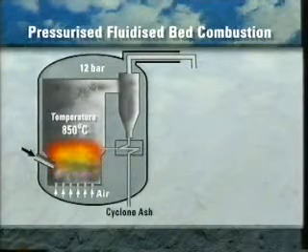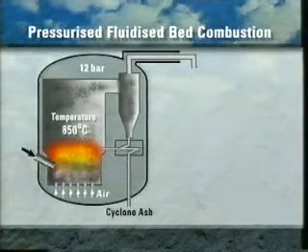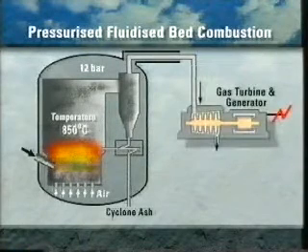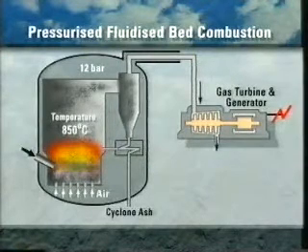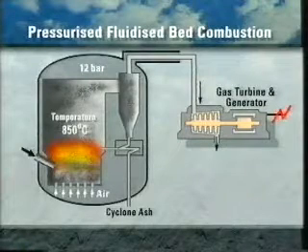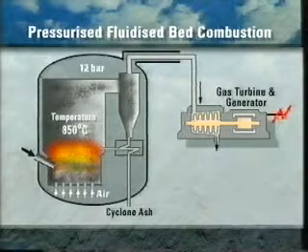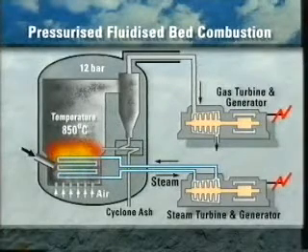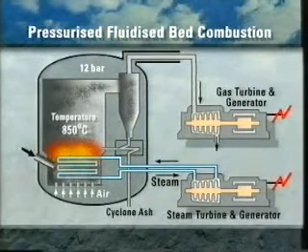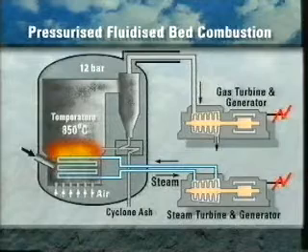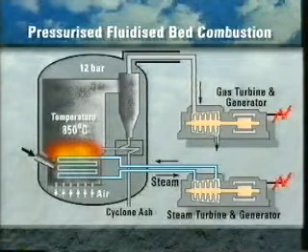The temperature of the fluidized bed is kept at about 850 degrees centigrade. Fly ash is removed from the combustion gases in cyclones. The pressurized gases then drive a gas turbine which supplies fluidizing and combustion air to the combustor and powers a generator. Heat extracted via tubes in the fluidized bed and also recovered from the gas turbine exhaust raises superheated steam which generates electricity through a traditional steam turbine.